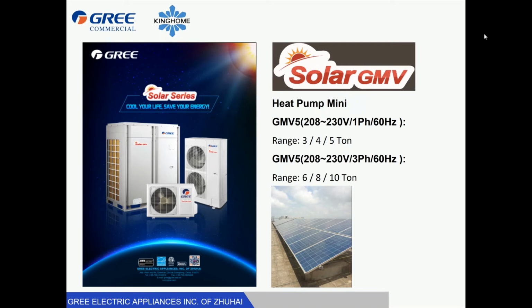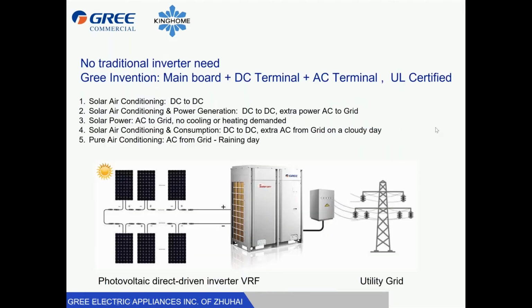So I'm going to jump right into the solar VRF. The 3, 4, and 5 ton mini VRF units are able to be powered directly by solar panels. And that is the same for the 6, 8, and 10 ton heat pump VRF units. So what does this mean? It means we can plug solar panels directly into the units with no need for a separate inverter. We can also plug AC power directly into the unit at the same time. This allows us to provide adequate power to the unit no matter what the solar conditions are.